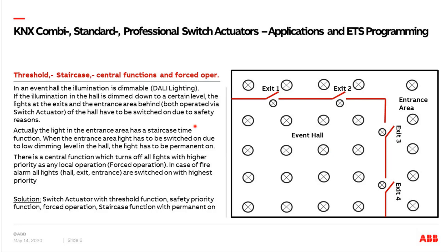All these functions can be done directly in the switch actuators. We use the switch actuator with a threshold function, safety priority functions — so-called forced operation — and the staircase function. I concentrate on the switch actuator and also the DALI gateway used here. The sensors behind are not so important — how you control this can be any push buttons, touch panels, or even presence detectors for the entrance area, for example. Now I share my laptop screen so you can see the ETS.